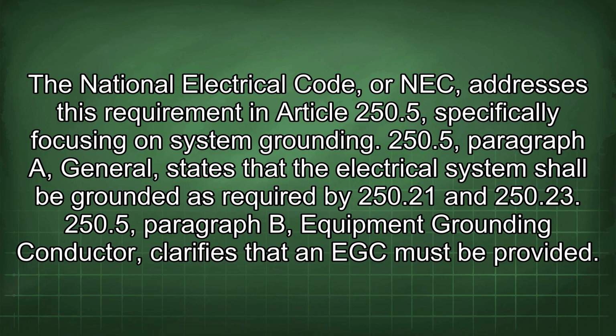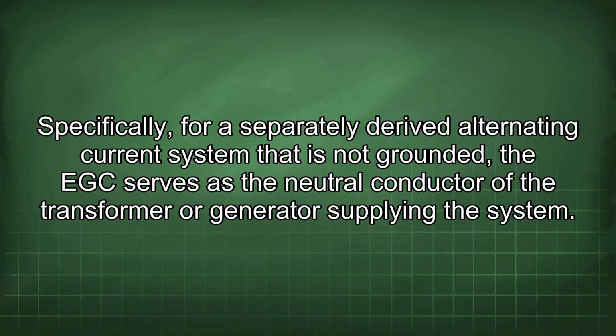250.5 paragraph A, General, states that the electrical system shall be grounded as required by 250.21 and 250.23. 250.5 paragraph B, Equipment Grounding Conductor, clarifies that an EGC must be provided. Specifically, for a separately derived alternating current system that is not grounded, the EGC serves as the neutral conductor of the transformer or generator supplying the system.